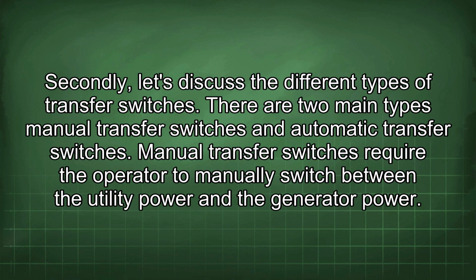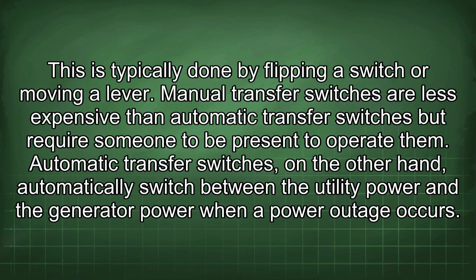Secondly, let's discuss the different types of transfer switches. There are two main types: manual transfer switches and automatic transfer switches. Manual transfer switches require the operator to manually switch between the utility power and the generator power. This is typically done by flipping a switch or moving a lever. Manual transfer switches are less expensive than automatic transfer switches but require someone to be present to operate them.